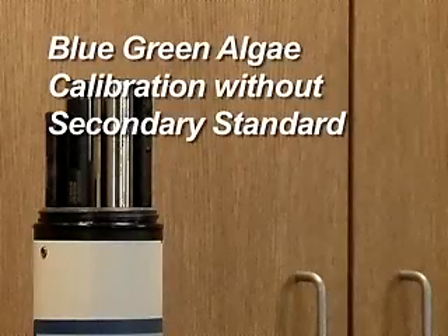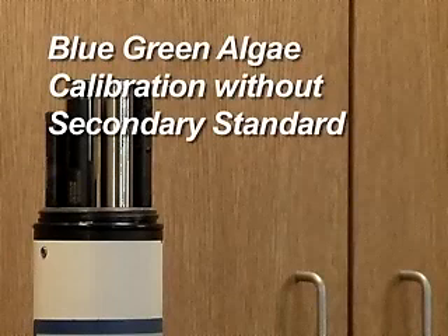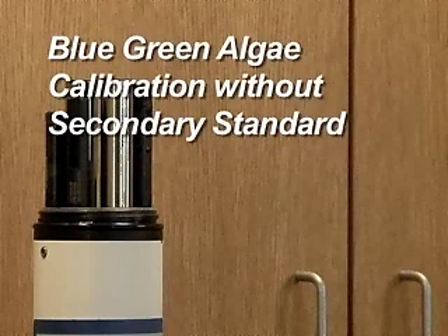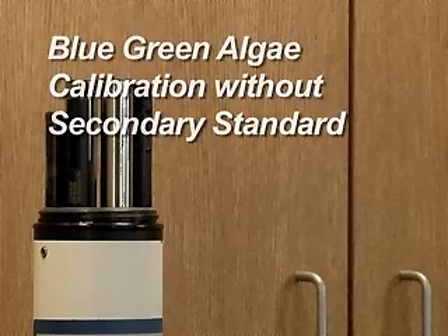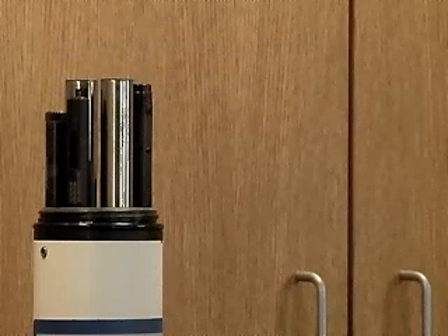Blue-green algae calibration without secondary standard. The blue-green algae fluorometers use the same principles but different wavelengths of light to detect different chemicals in the sample. The freshwater fluorometer emits orange light and detects the red light emitted by the pigment phycocyanin. The marine fluorometer emits green light and detects the orange light emitted by the pigment phycoerythrin.